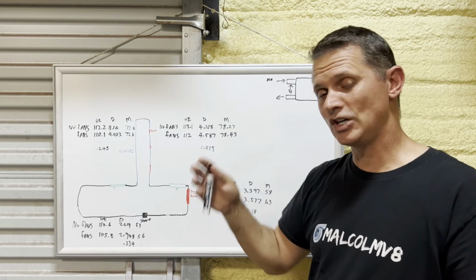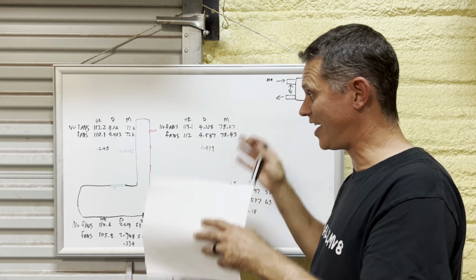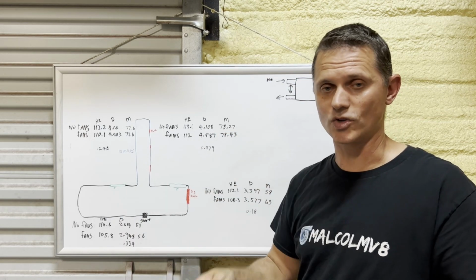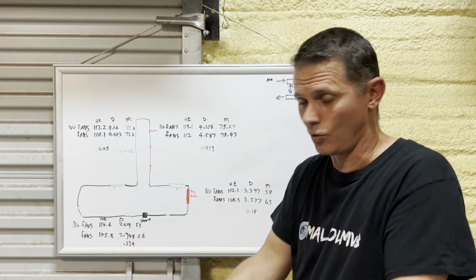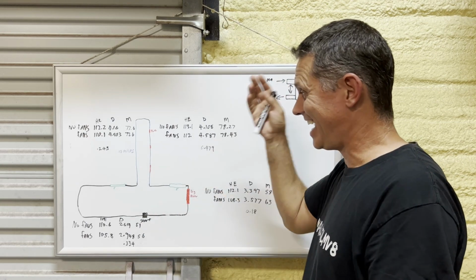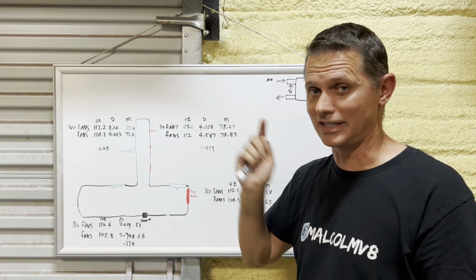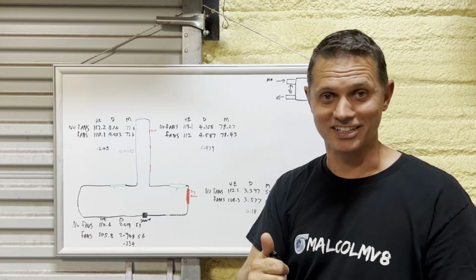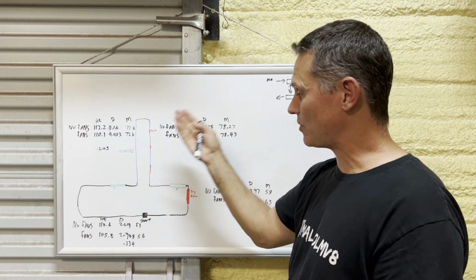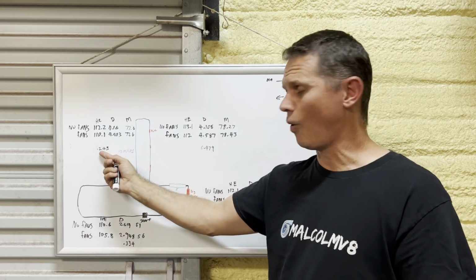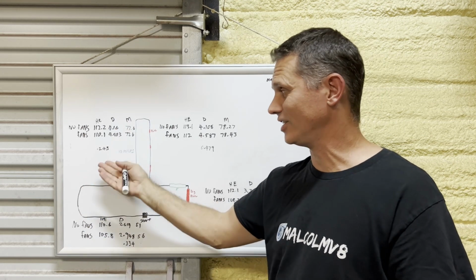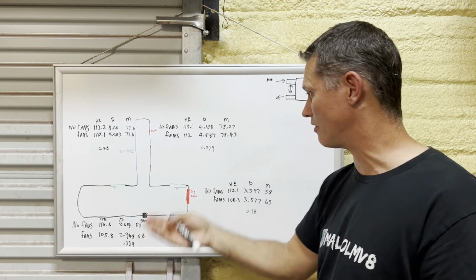That's a 0.479 improvement. The whole premise of the video was that fans make the heat exchanger worse, that they hurt cooling and break things. Our testing says quite the opposite — that's not true, myth busted. You actually get an improvement. Granted, it's only about 0.2 of a degree, but it's still an improvement, not a failure of the fan.